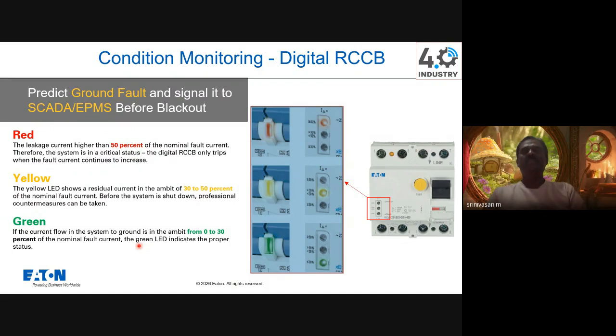Also, we have another interesting component. It's called the digital RCCB. Normally, with the conventional electromagnetic type RCCB, if the leakage current is less than 30 percent, the RCCB will not trip. If the leakage is between 30 to 50 percent of the leakage current, still it will not trip. But the moment the leakage current increases from more than 50 percent to 100 percent, then the RCCB will trip. The point to be noted here is that the conventional electromagnetic type RCCB trips without giving any warning signal. Suppose it is feeding any critical loads, you will lose the power supply. That's not a good sign.